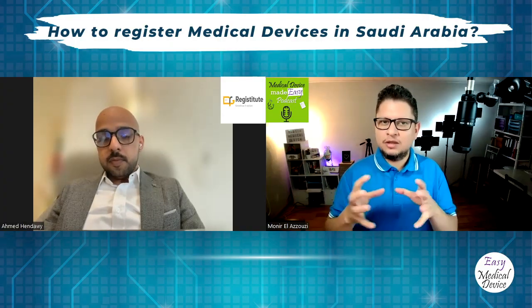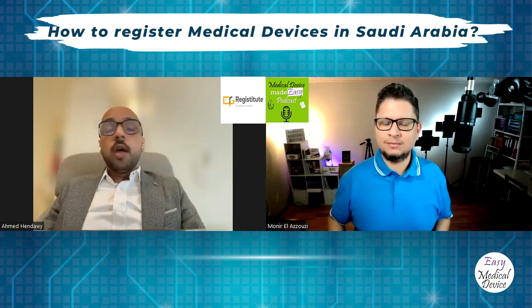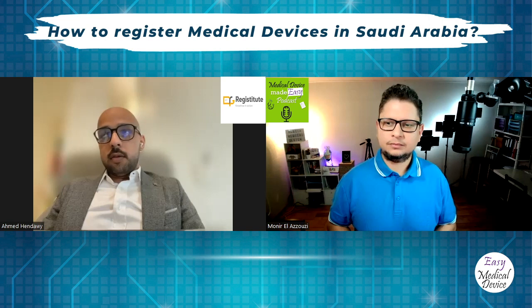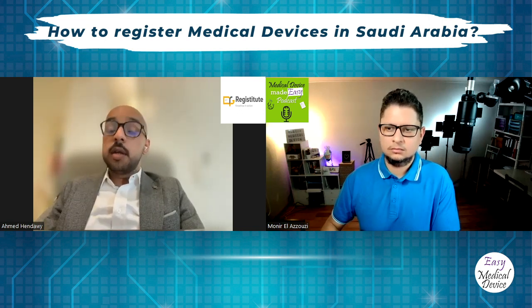So an importer is needed, and an authorized representative is needed. They should both be in Saudi Arabia. Do they need to communicate together, or can they be really separate with no need at all for them to work together? Yeah, so in all my years of working in Saudi Arabia, communication from the authorized representative to the distributor or importer is very, very minimal. They barely communicate. They don't need to, because the authorized representative deals with the manufacturer and SFDA. There are no responsibilities that fall on the authorized representative to communicate with the importer, unless there is a post-marketing activity, and most of the time this is done by the manufacturer.